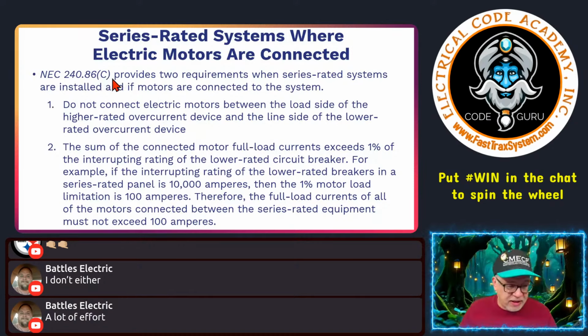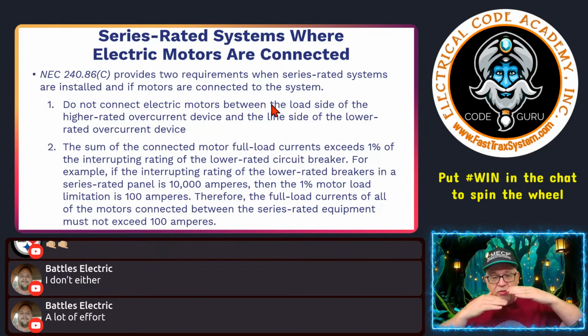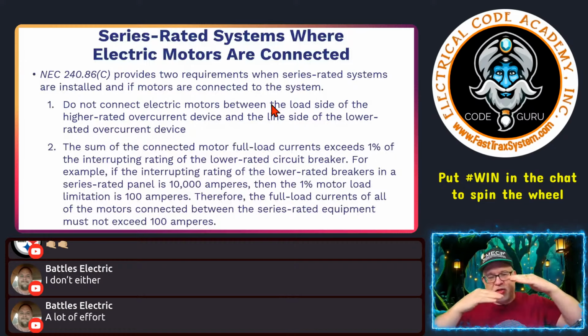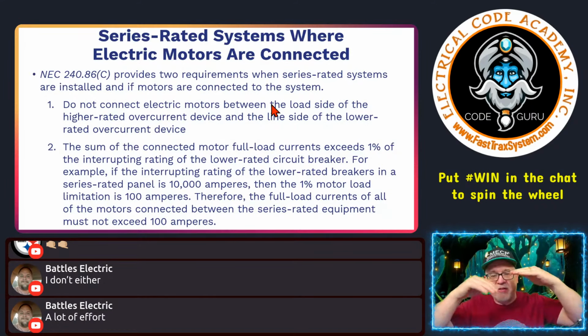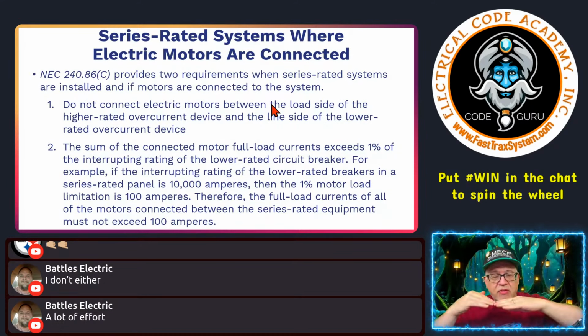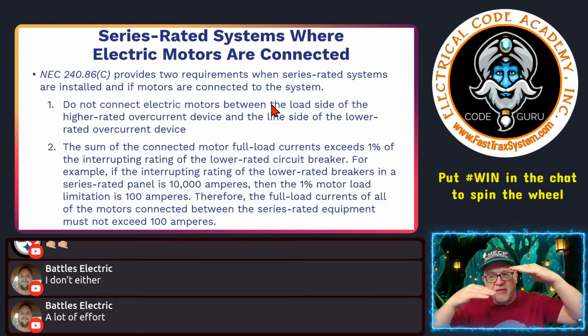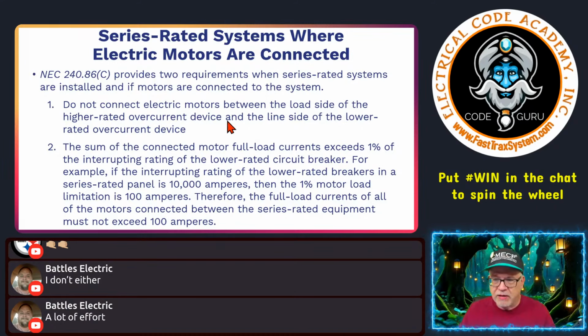240.86(C) in your NEC provides two requirements when series rated systems are installed and motors are connected to the system. Again, remember, because it's series rated, you have the main, and you might have a branch circuit breaker going out to the motor. It may be series rated, so it's going to be less than the main as far as the AIC. So it may be a 22,000 main and a 10,000 amp breaker. That's fine because it's series rated. However, if you're using it on an electric motor circuit, you have some caveats you have to be aware of.